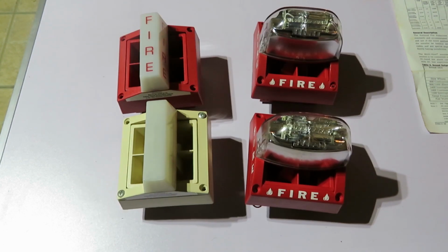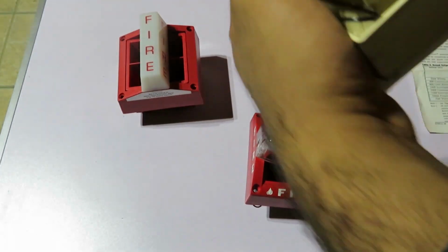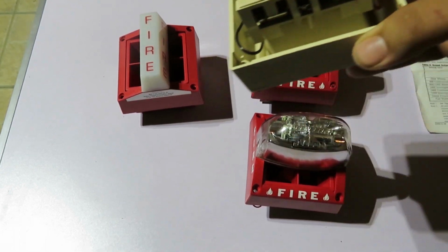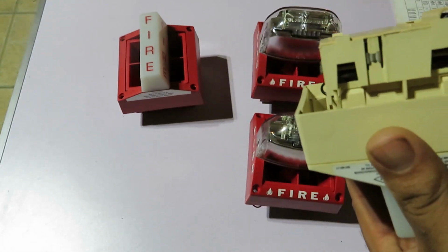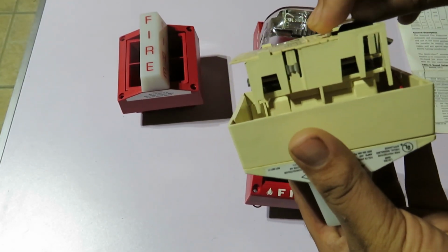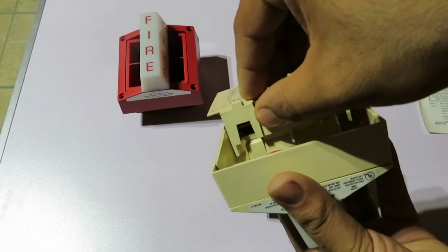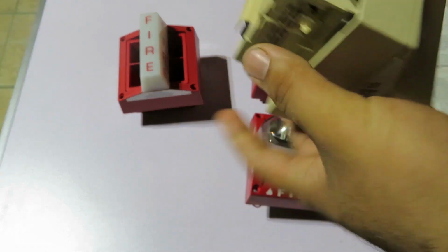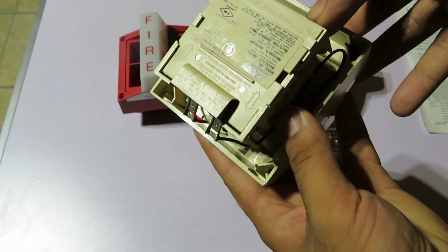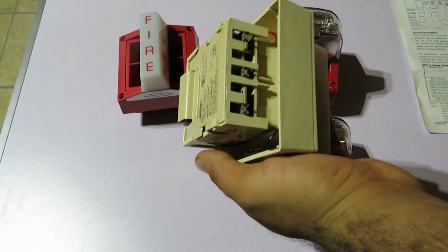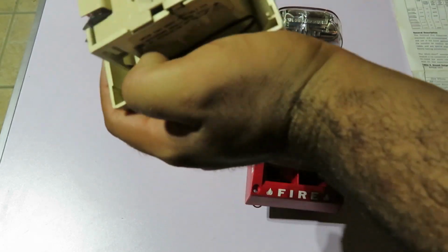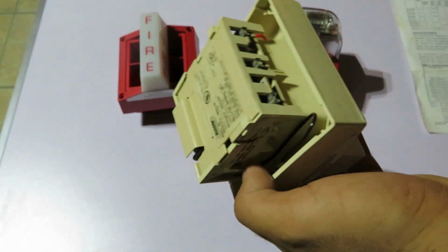Now, on your System Sensor MASS, your default tone will be 800 continuous. So it will be only clip B and C, and then you're going to have an extra clip to the side. Now this is the clip holder. What this does is store your clips, so if you need to change your tone, you simply take it off and you plug it in, and basically, that changes the tone from 800 Hz continuous to slow whoop. So basically, pretty simple, straightforward.